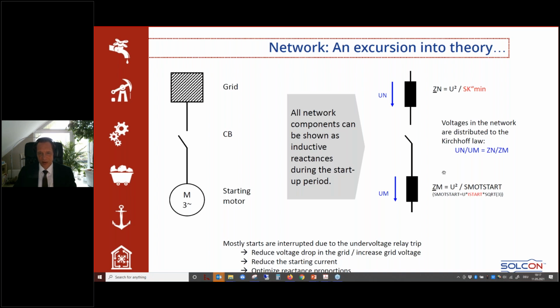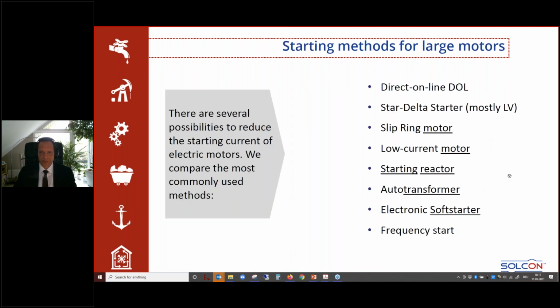So this can be done with various means, and these are as follows. In 95% of the cases, you see direct on line. And with this, most customers are happy. But if not, you have various means of reducing the starting current. The most common means of reducing starting current is a star delta starter. Then you can do something on the motor, which is either a wound rotor motor or slip ring motor, as we say here, a low starting current motor. Then you can apply a starting reactor or an auto transformer. Or here you have the means of electronic soft starters, which is the classic soft starter where you are reducing the voltage, or frequency start, which is the IGBT starting. Okay.